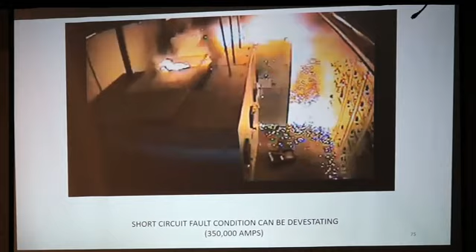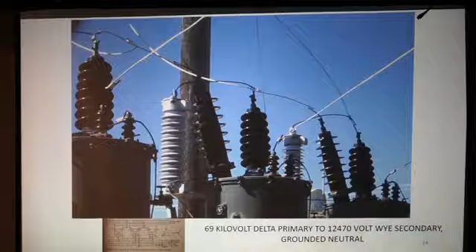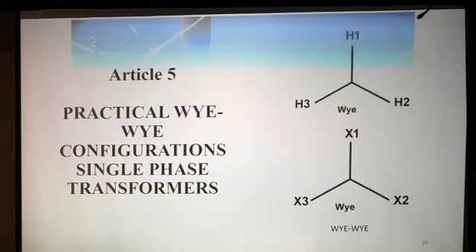This is a delta Y. On the way up here, you can see the secondary bushings on the transformer. One goes up to the phase conductors, and the other bonds to the tank and connects to the substation ground plane. But there's also a neutral, so what they're doing here - the idiots - is running all their zero sequence current, because it's a 4-wire Y-connected load, through the substation metallic structure before it can find its way back to the transformer, which is nonsensical. This is the bad way of doing things.